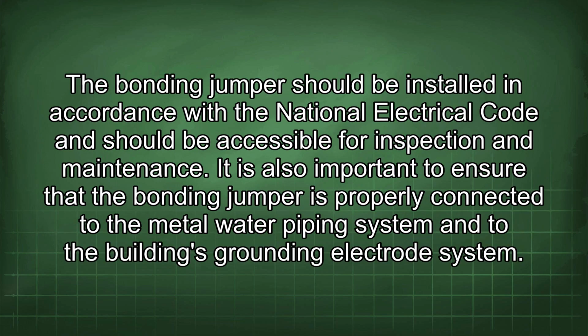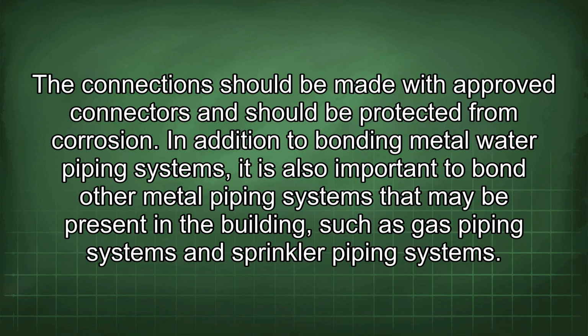The bonding jumper should be installed in accordance with the National Electrical Code and should be accessible for inspection and maintenance. It is also important to ensure that the bonding jumper is properly connected to the metal water piping system and to the building's grounding electrode system. The connection should be made with approved connectors and should be protected from corrosion.